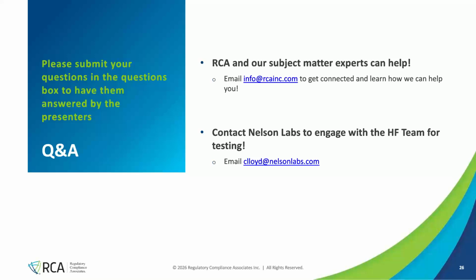Design changes intended to reduce a specific risk that has already been identified will typically require some human factors evaluation to verify it was effective in mitigating that risk. It might not be a full summative, but some evaluation with representative users in a representative use environment to confirm that the change you've made did what it was supposed to do.